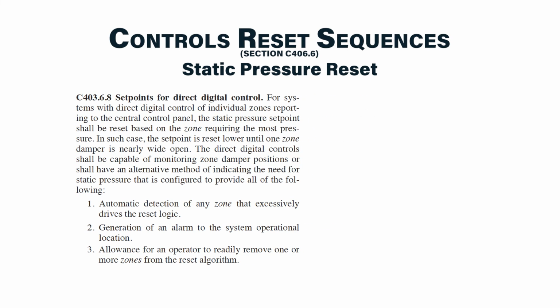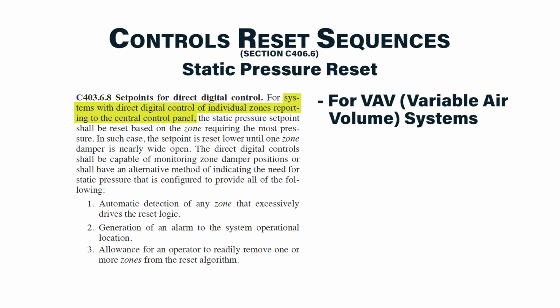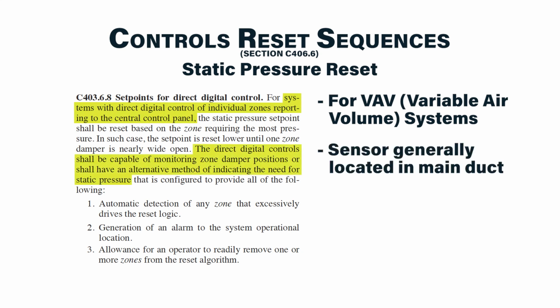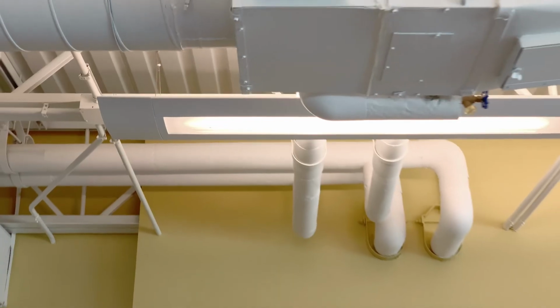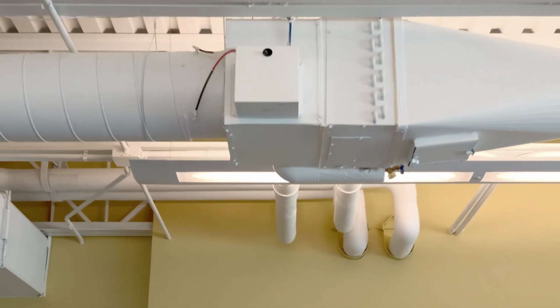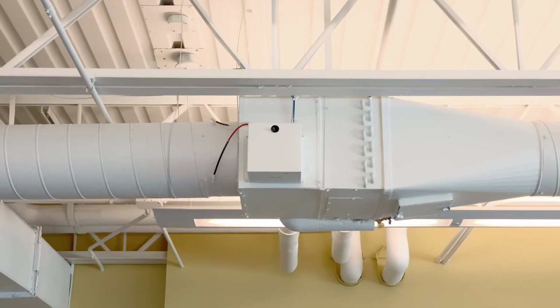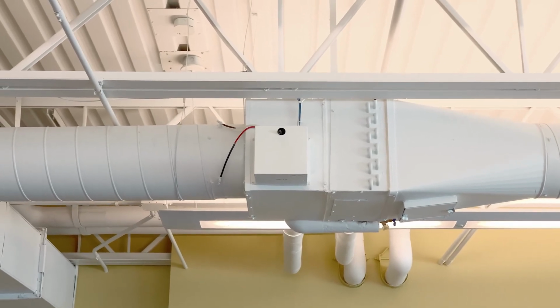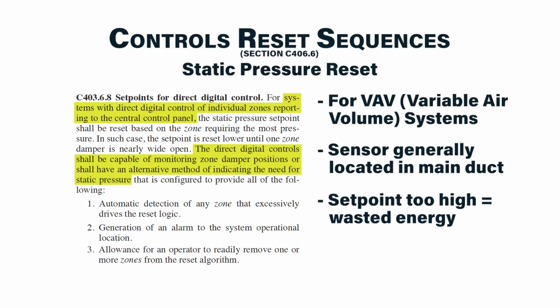In a VAV system, the fan speed is usually controlled to a static pressure set point determined by a static pressure sensor in the main duct. This ensures all VAV boxes get sufficient air. If the static pressure set point is set too high, then the fan will use a lot of energy while the VAV box dampers will try to close further to prevent too much air from overcooling the space.